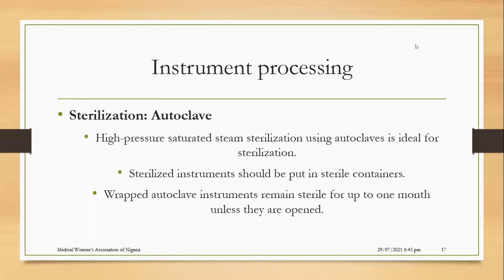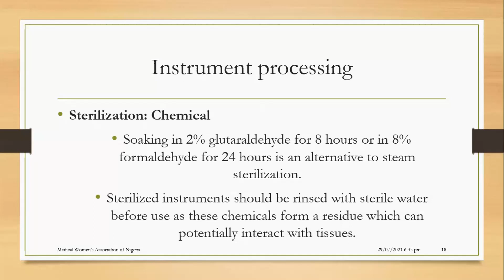Then the other form of sterilization is chemical sterilization. You can soak it in 2% glutaraldehyde for about 8 hours, or in 8% formaldehyde for 24 hours. And these usually come in commercial packs, but they are usually very expensive, but they are usually more readily available than autoclaving, because for autoclaving, you need a machine to autoclave. Then if you use chemical sterilization, it should be rinsed in order to remove the residue of the chemical, so that you won't cause any harm to the patient.